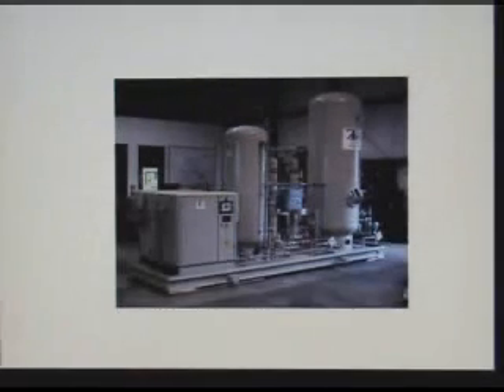There's another package. Again, you have a wet receiver, the dryers, and then you actually have a dry receiver, which is what feeds the rest of the plant. And the reason that you have the receivers is you have a volume chamber to allow some time as you go from your high set point to your low set point on pressure, and it avoids rapid cycling of the compressors.